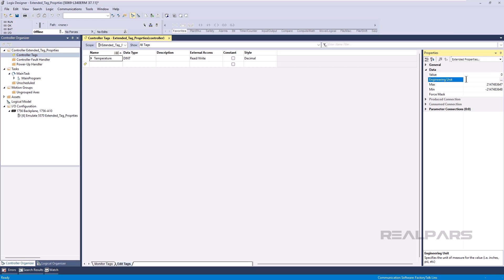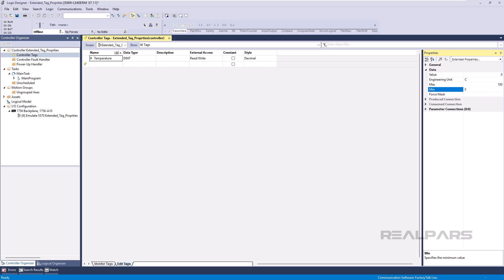Once enabled, the value of Extended Tag Properties can be configured in the Data section of the Tags Property panel. It's important to note that Extended Tag Properties can only be modified through the Tag Editor. They cannot be modified dynamically at runtime by application logic or modified through the HMI.